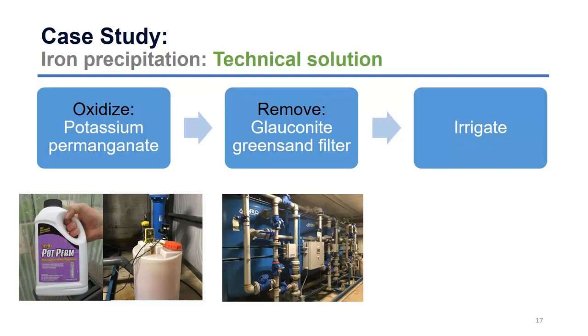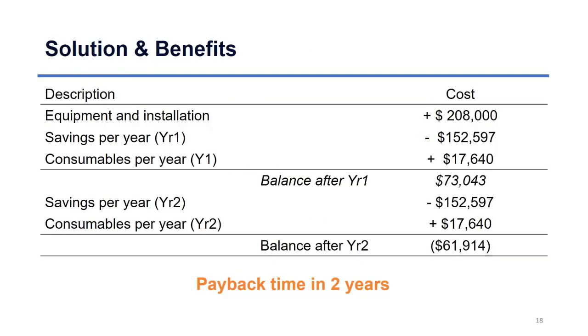I'm going to talk shortly about what other options are, but just in general, whenever you're trying to remove any type of iron from your system, one of the things you want to consider is: is there a way that I can easily and inexpensively make that a solid, and then filter it out? That's the first thing you want to think about, just because it's easier than trying to actually capture and remove those ions, say with something like reverse osmosis, which is a technology that also works, but it's much more expensive, and also requires a high level of engineering knowledge to manage.